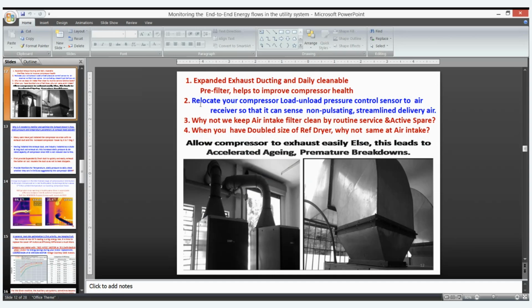The high cost option is, you can discuss with your OEM. If we are able to double the air compressor's air intake filter, definitely it can withstand for a longer time, and the Pascal drop across the filter will be less, and definitely the flow will be almost 100% of the rated delivered flow, even after say 3 months, by condition monitoring. So both the aspects are there.